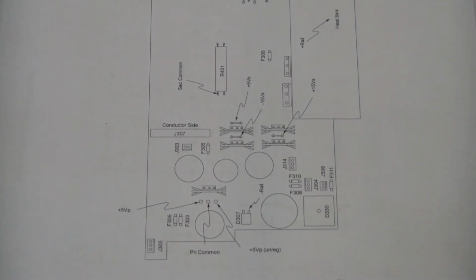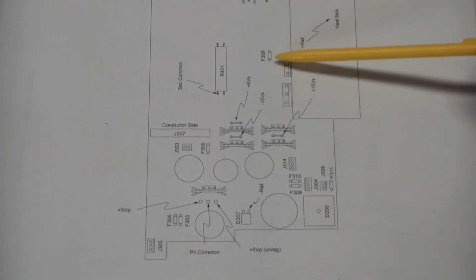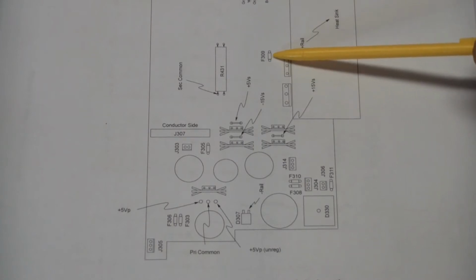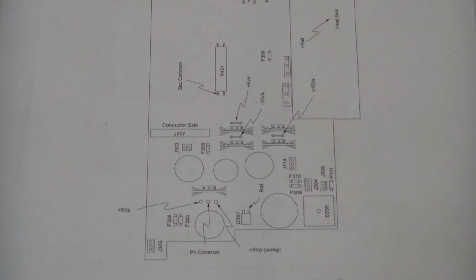However, looking at this closely, there is another fuse in the middle, F309, and I searched through the manual for F309. There was a fleeting reference to it, and if you read that paragraph, it actually told you that F309 is the output fuse of the main voltage output on the device.